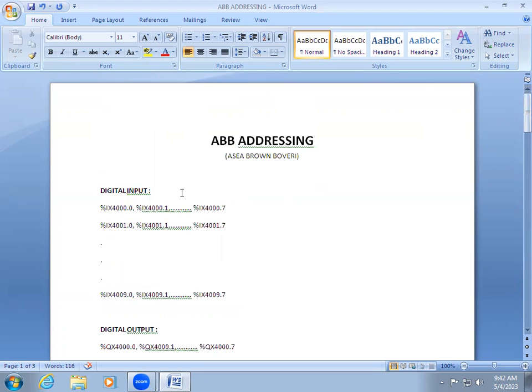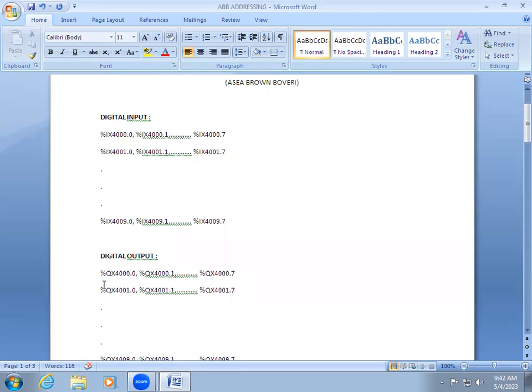For digital input, the address starts from %IX4000.0 till 4000.7 — that means 4000 is the channel and point zero is the bit. Each channel has eight bits. Suppose the first eight addresses have been used; the next address you have to use is 4001.0. The same way goes for digital output: %QX4000.0, 4000.1, and so on.